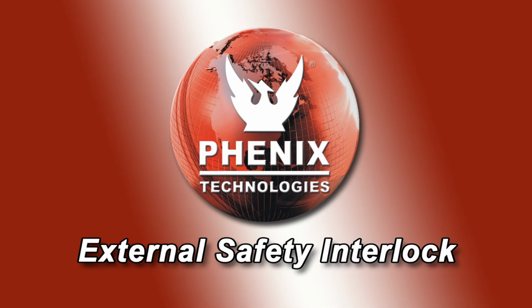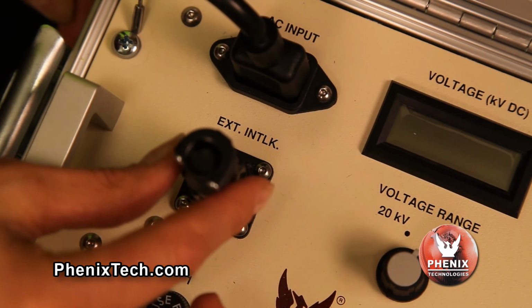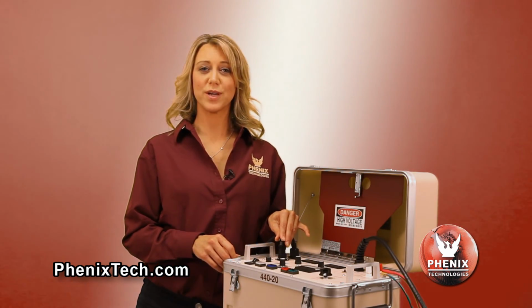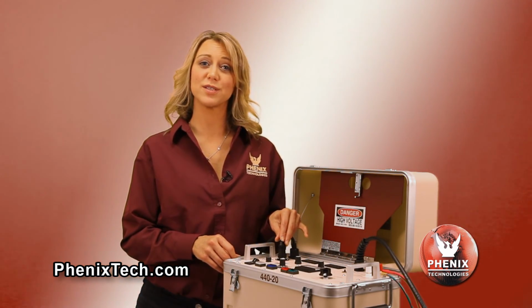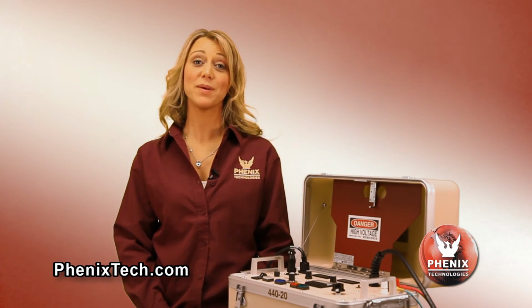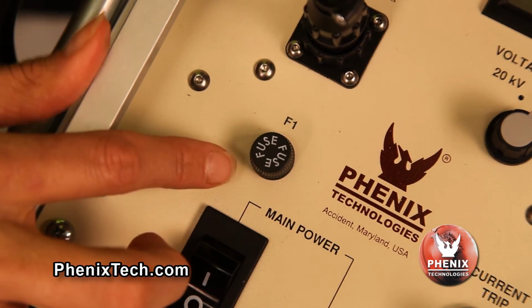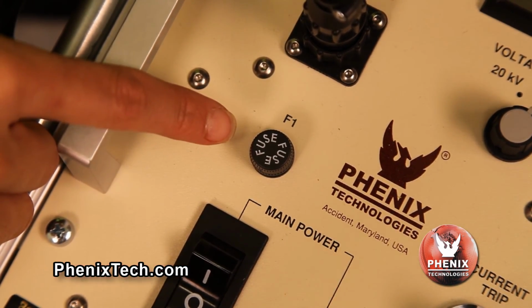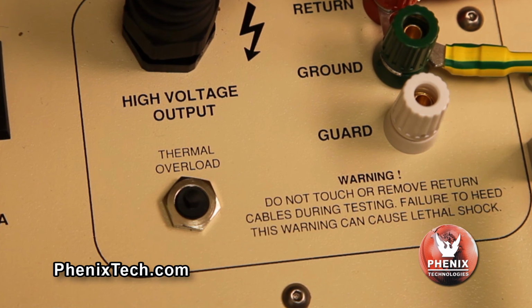The external safety interlock. The Hipot is shipped with a jumper in the connector that allows the operator to use the Hipot without an external safety interlock circuit. If an external interlock safety device is desired, such as a foot-operated switch, you would remove the jumper and replace it with the safety switch device. Our Hipots have a built-in discharge circuit. This feature allows any residual charge that may remain on the test object to discharge after the Hipot is turned off. The fuse is sized to protect the control power circuit. The thermal overload protects the high voltage transformer.